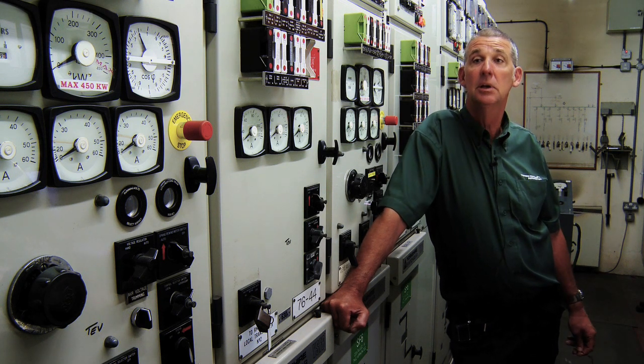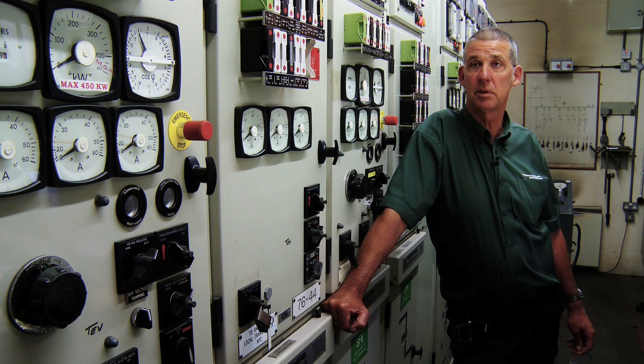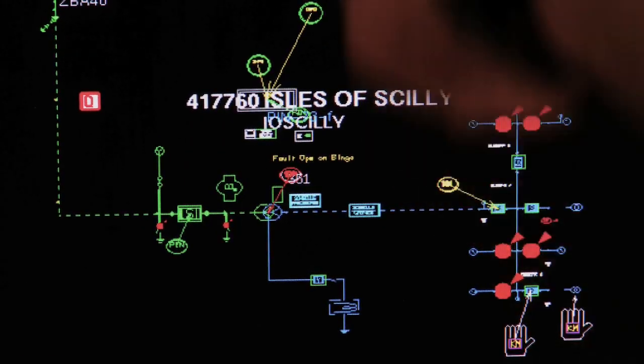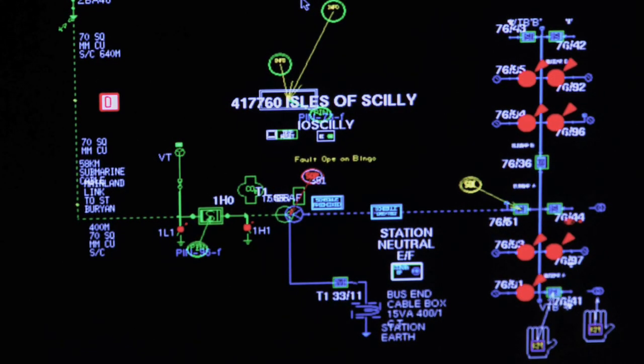The nearest bulk supply point to the Isles of Scilly is Hayle, where it's transformed down to 33 kV into West Cornwall via an overhead network, then from Land's End to the Isles of Scilly via a submarine cable, into Porthcressa at St Mary's, and then up to the power station where it's transformed down to 11 kV and distributed through the islands.